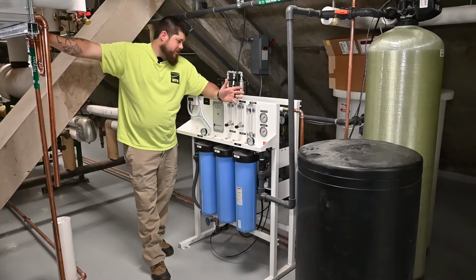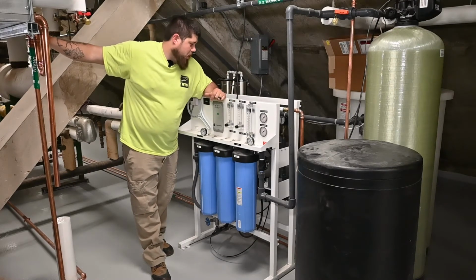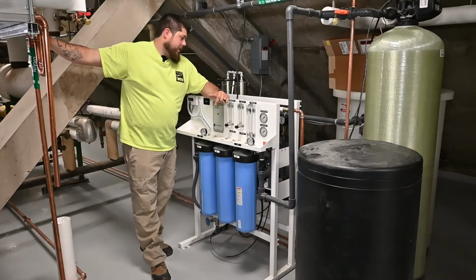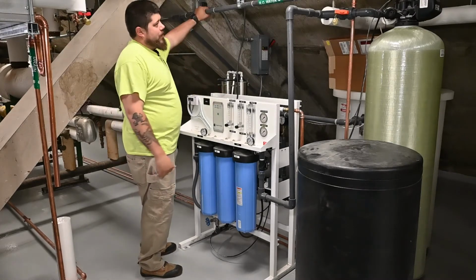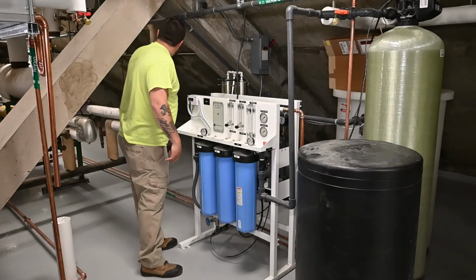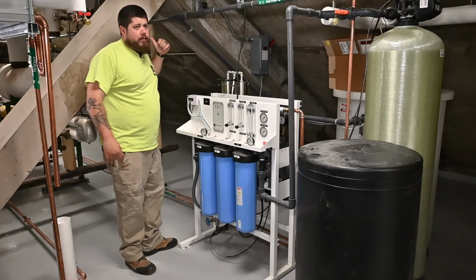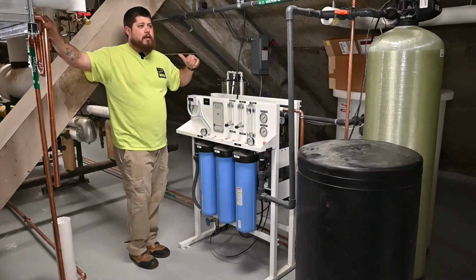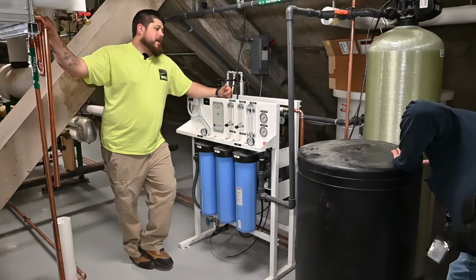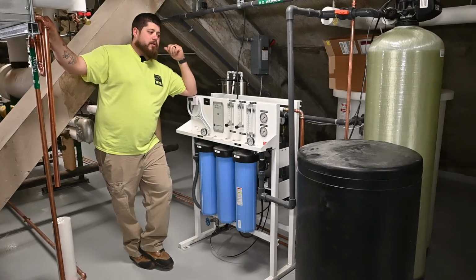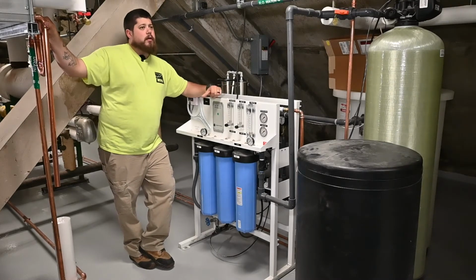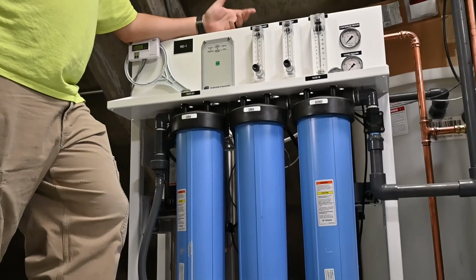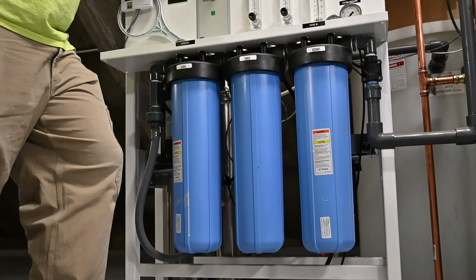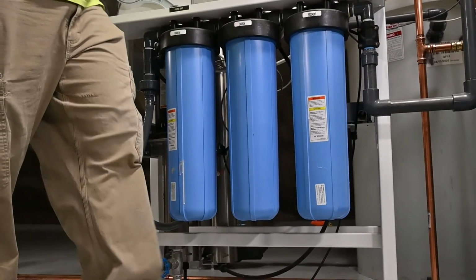If for any reason there's a clog, there's a manual ball valve on the bottom that you can tie off to. Down the line on this line set, further down, you can see a manual ball valve. If for any reason you need to dump this entire tank, the recommendation is to tie off to that ball valve downstream with a hose, go to a drain, open up, and run the pump. You can manually shut this off. You can even just kill the water right here to it and then start running that pump.